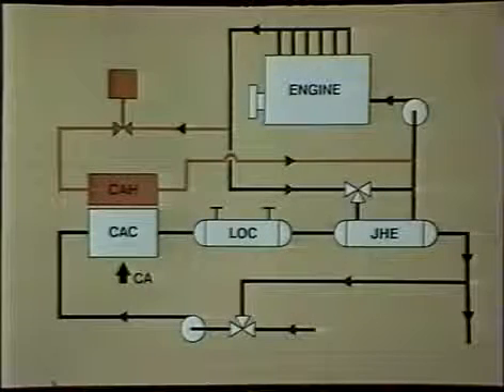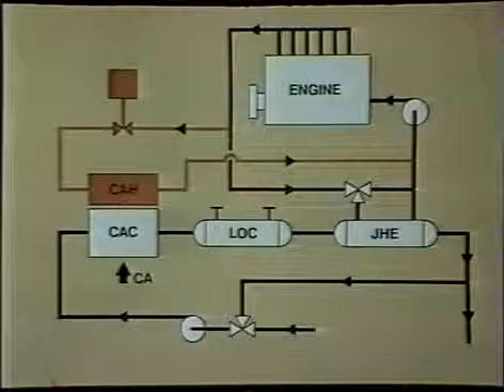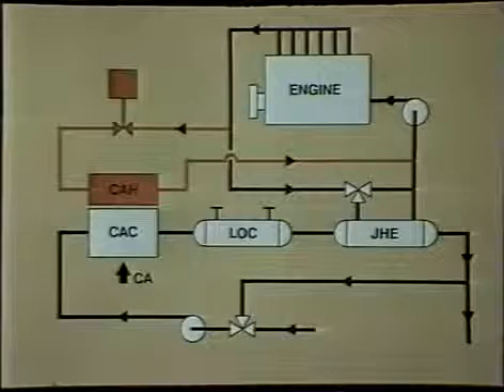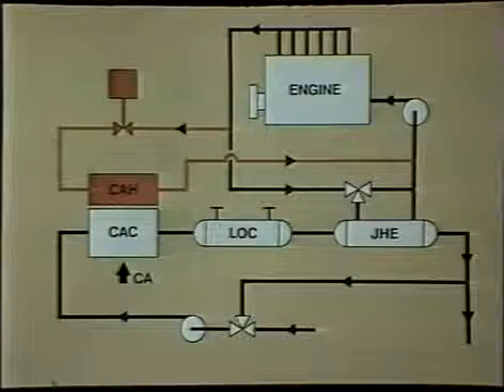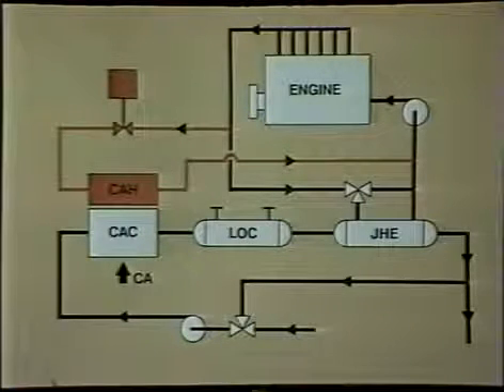To ensure optimum combustion at light load and prevent cold corrosion, WH Allen offers engine cooling systems incorporating charge air temperature control. The design retains optimum control of the jacket water and lubricating oil system temperatures. This ensures that the charge air temperature as a function of load follows a predetermined line, dictated by a simple electronic unit which monitors engine load and charge air temperature.